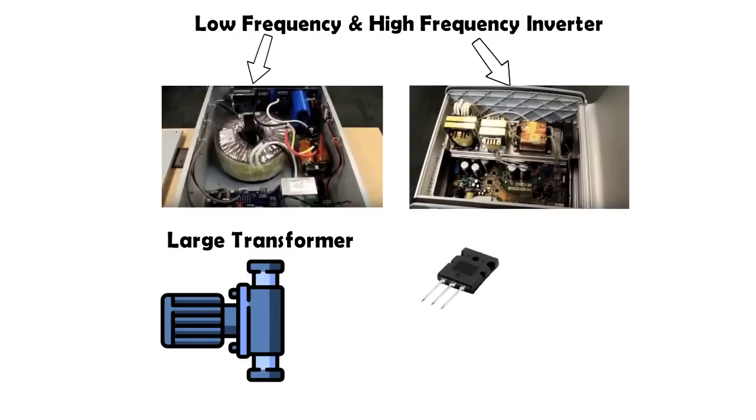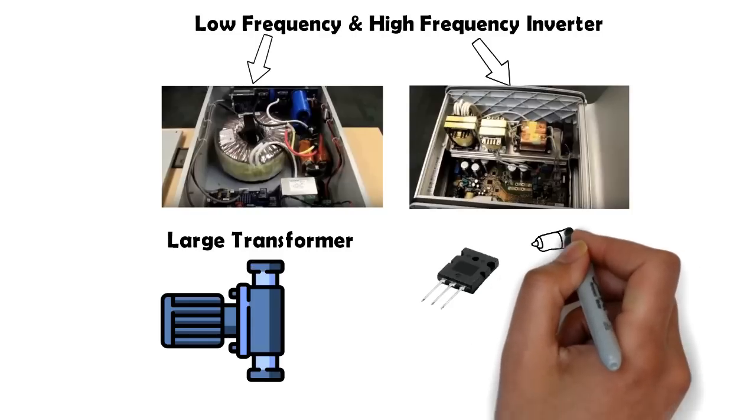In a high frequency inverter, there are almost twice the number of components compared to low frequency inverters. Nonetheless, they are still smaller and lighter overall because of the absence of a large central transformer. They are not very well equipped to handle industrial loads, and therefore if a large pump, a motor, or an air conditioner is required to be run, then a low frequency inverter is a better option.